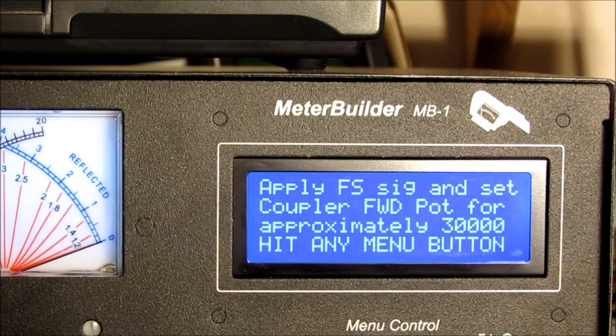What I'm going to do now is set up my reference meter. I'll be using an Alpha 4510 as my reference meter. Any accurate reference meter can be used for the custom calibration process, and I'll use that to determine when I'm applying 500 watts. This coupler is in tandem with the alpha, and at that point I know my output power is at my maximum full scale value, which is where I'll tweak the trim pot on the coupler forward port to a value of approximately 30,000.